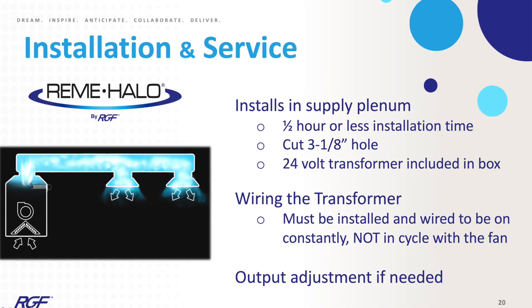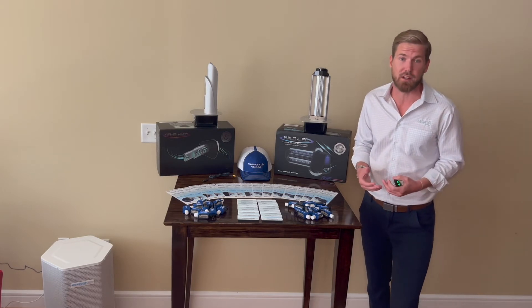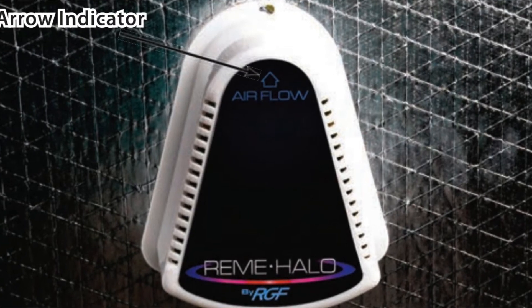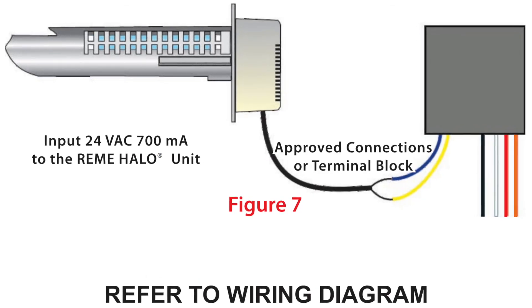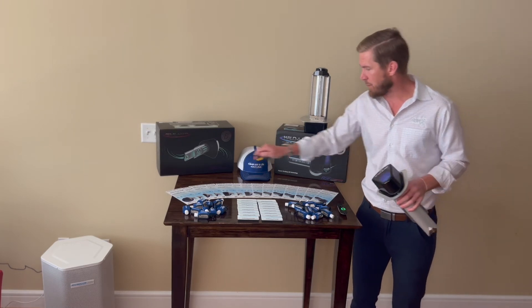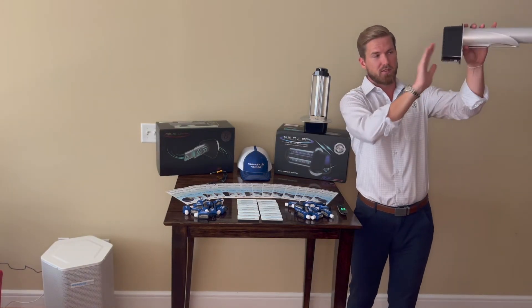REME HALO installation and maintenance is super simple for the HVAC contractor. The installation should not exceed 20 to 30 minutes. Simply cut out a three and one-eighth inch hole in your supply plenum, insert the system in there, then wire it to the transformer provided in the box. RGF recommends changing the cell of the REME HALO product every two years. As mentioned, you're mounted in your supply plenum.